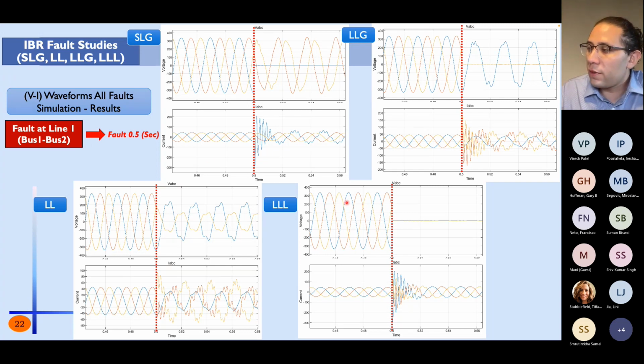And going back, in the fourth figure, I'm showing the triple line fault, where we can see the voltage and the current. Here we can see how the voltage actually goes to 0, which is expected because of the three-phase fault. But to the controllers, if we just measure the current, we can misrepresent that there's no fault here, but we do actually have a fault. So, as I showed before, those are very critical cases where the responses get affected and relays won't detect.